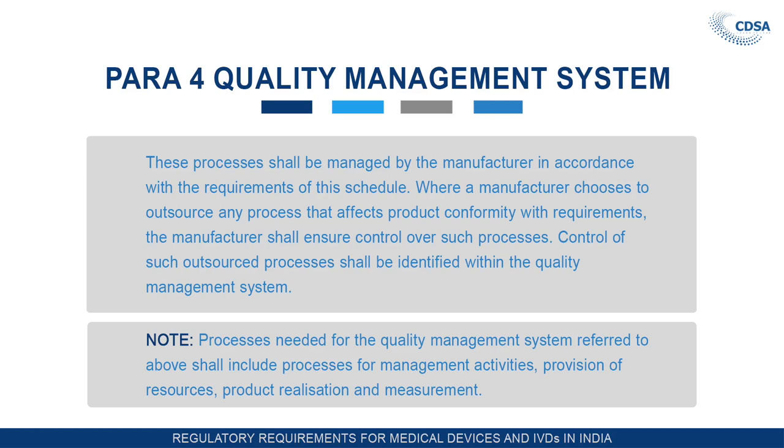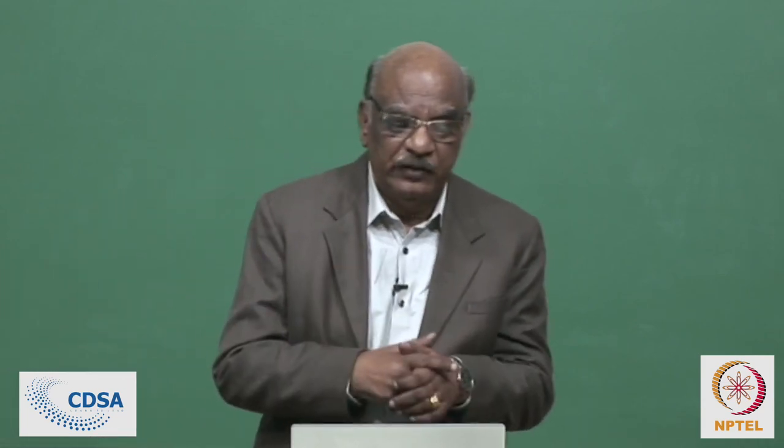The second line is very important. It says that when a manufacturer chooses to outsource any process that affects product conformity with requirements, that means I manufacture a medical device, and a part or a component of it is being manufactured by somebody else under my contract. Now, in that case, I am responsible for the QMS of that contract manufacturer's process also. So, I have added responsibility for that.